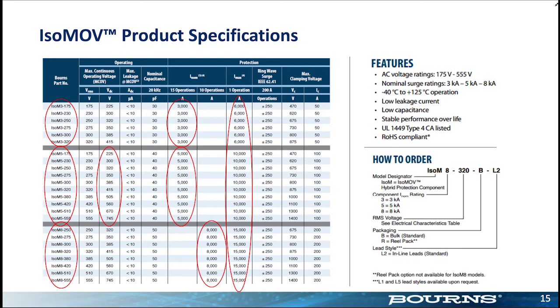All right, so we have another question here that asks, with the introduction of the IsoMOV, will your GMOV go away? I'll take that one. As you saw, the IsoMOVs go down to 200-something volts. And as I alluded to, MOVs have current limits and voltage limits. The current limit is due to current density, right? So the bigger devices can handle more current, so the size, the diameter of the disk. But the voltage limit is based on the thickness, right? There's an electric field in there. So the thicker devices can withstand more voltage.